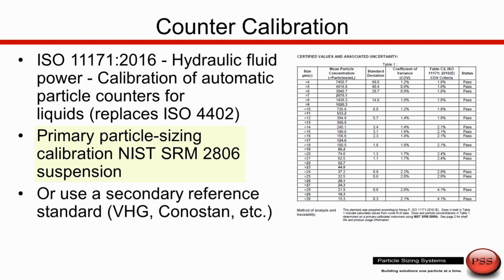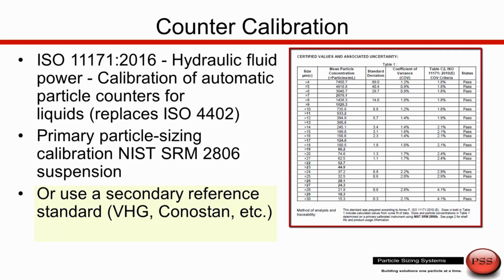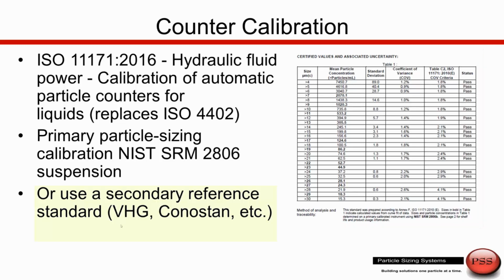It's also a bit more expensive than many people are happy with, so there are also secondary reference standards available through various other laboratories, such as the one shown here. The table you see on the right is actually from the certificate of analysis from one of these secondary standards, showing at various size ranges the number of particles per ml. The calibration procedure therefore is you can go in and adjust the voltages to make sure that at given size ranges you match the number of particles per ml from the certificate of analysis. So the secondary reference standards are used more often than the primary standard. And the difference here, the people who create these secondary standards are using an instrument that was calibrated with the primary standard. But the majority of the customers who we know in the field will typically be using these secondary standards when doing field calibrations.